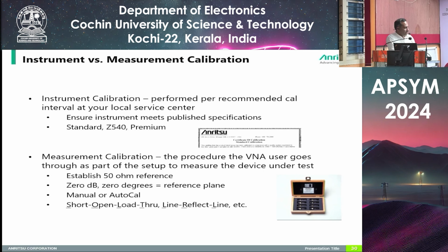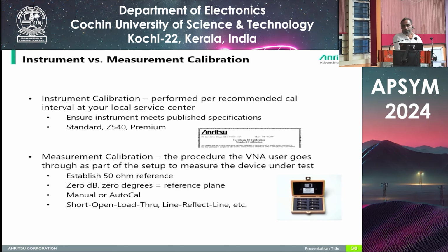So this is the calibration kit, which will include open, short, load, male and female both, with the connectors. Okay. So whenever you are using a VNA, you should use a calibration kit with the cables. And we will recommend phase stable cables, where you will get a better measurement.